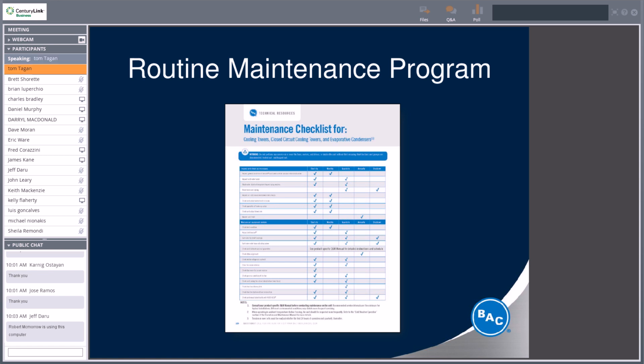Again, they always recommend cleaning and checking the general condition of all the equipment, whether it's the fan motor or the inside of the cooling tower. You want to make sure that your fan blades are not loose, and that there are no cracks in your fan blades.